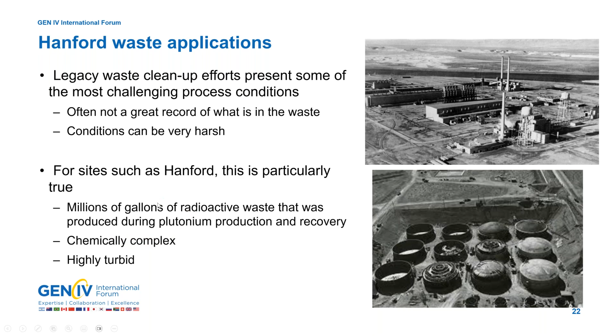Some of our past demonstrations: back in the early 2000s, we had a task to measure, using Raman spectroscopy, the oxy-ions in the waste during a salt retrieval campaign. This was designed to measure the salt cake being retrieved from a source tank, which was going to be immobilized and run through a pipe to the vitrification plant. We designed a sensor that could measure 9 analytes, the oxy-ions, in a skid mounted out in the tank farm, designed to run up to 40 gallons per minute in flow rate.